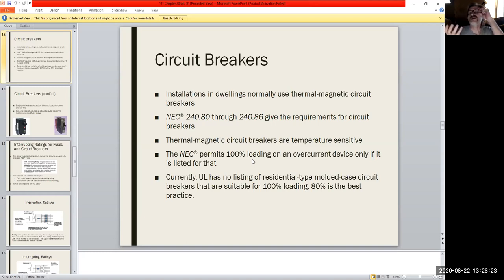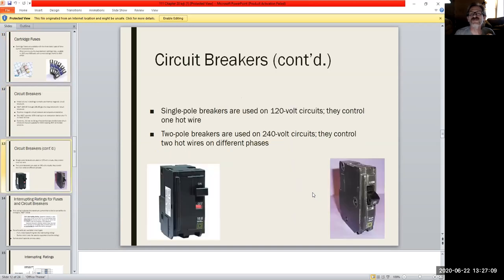So if you were planning on having something like that, you would have to go out and buy a specific circuit breaker designed to handle that loading factor. And it's going to be a little pricier, of course, than your standard style, because it's going to be more sensitive as far as the little electromagnetic coil it has inside. But typically what we plan for is an 80% factor. That's very standard for a house. So unless you're actually planning for a specific area to have this 100% loading, your best line is 80%. There's another area where we don't follow that rule, but we'll get into that in a little bit.